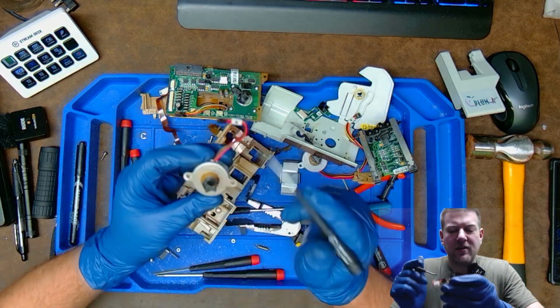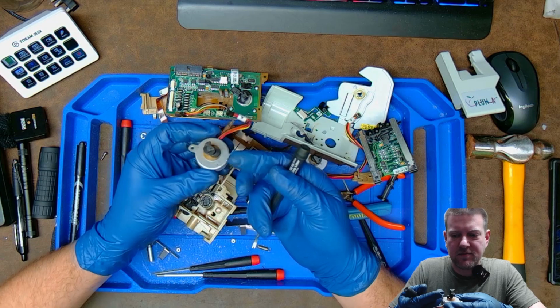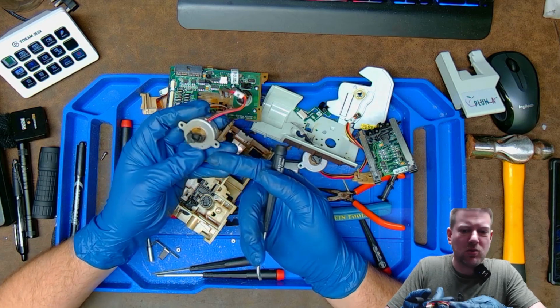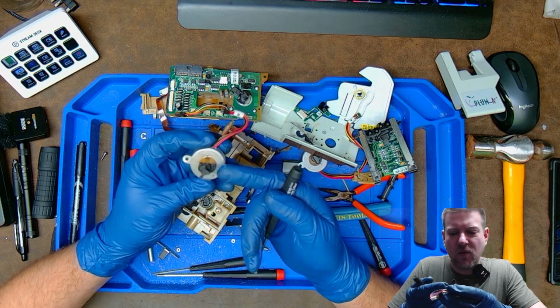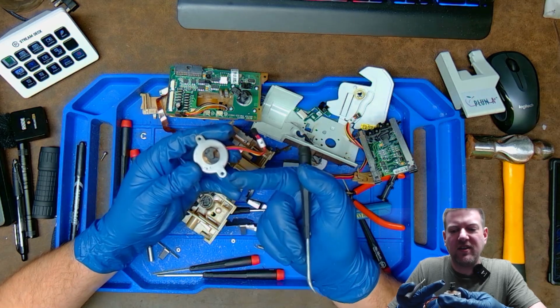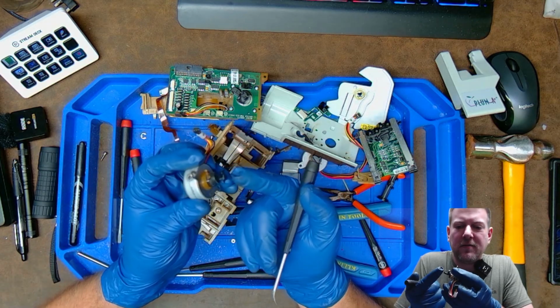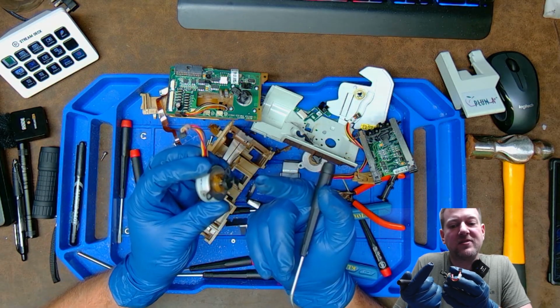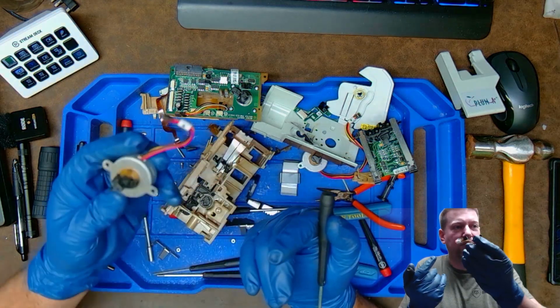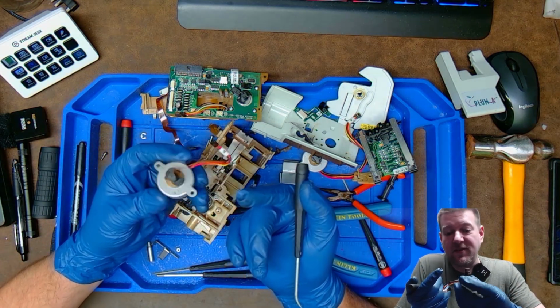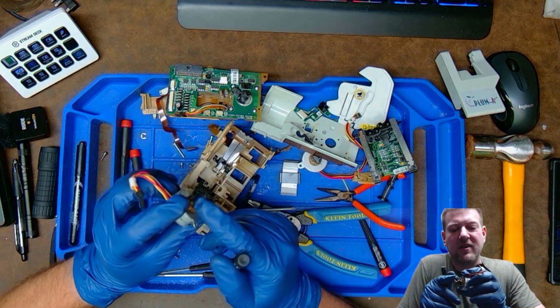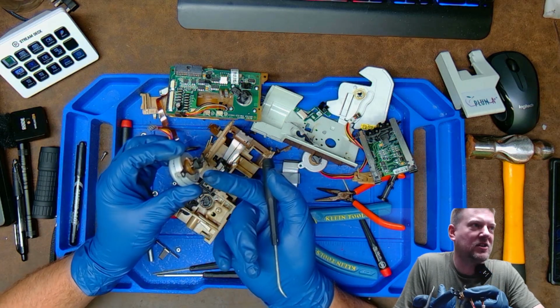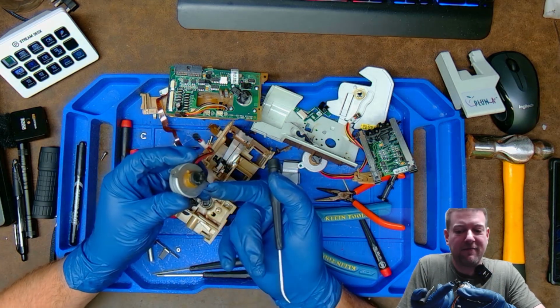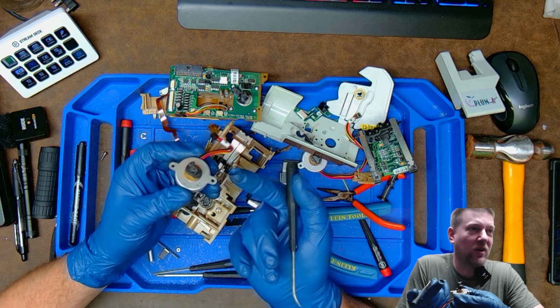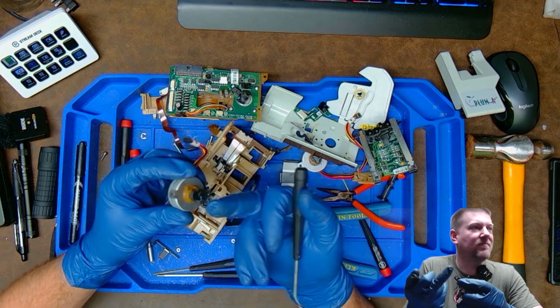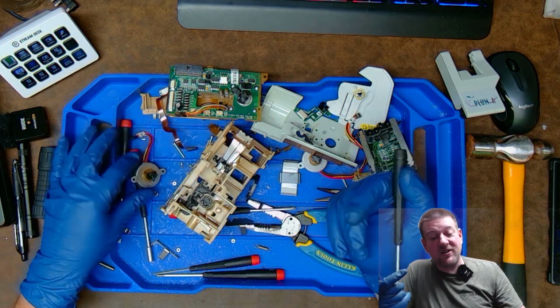This guy, you can tell that there is some goo on it, and that is old lubricants and wear and tear. Like some of that is dust from some of these composites. They're just wearing, you know, friction over time. So these pumps are going to have a life expectancy because of the very limited amount of lubrication. Yeah, take a look at that. That's not graphite, folks. Nope, that's way too chunky. That is composites that are wearing on each other.